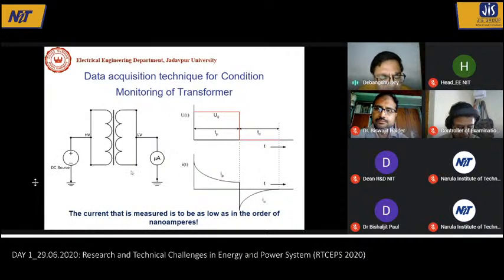More clearly, this is the winding. As we have taken electrode 1 and electrode 2, across electrode 1 we give a DC supply at high voltage, of the order of a few kilovolts, and then we record the current. Whenever the voltage is a step voltage of a few kilovolts, the current will be something like this — this is IP, the charging current.